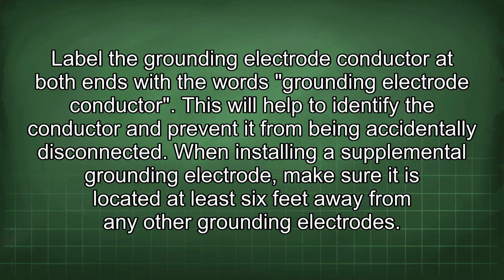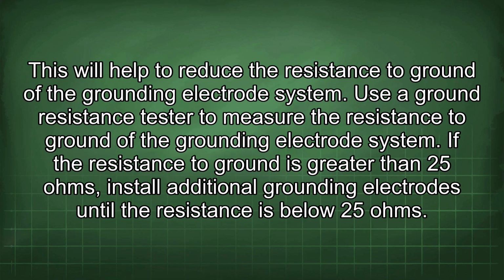Label the grounding electrode conductor at both ends with the words "grounding electrode conductor." This will help to identify the conductor and prevent it from being accidentally disconnected. When installing a supplemental grounding electrode, make sure it is located at least 6 feet away from any other grounding electrodes. This will help to reduce the resistance to ground of the grounding electrode system.